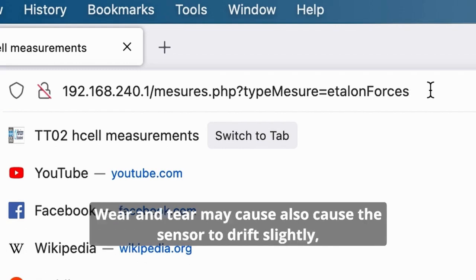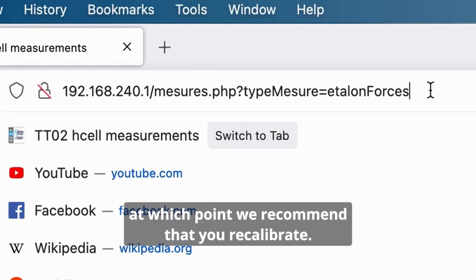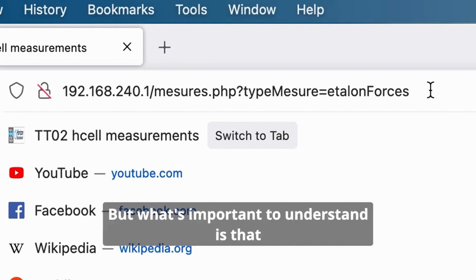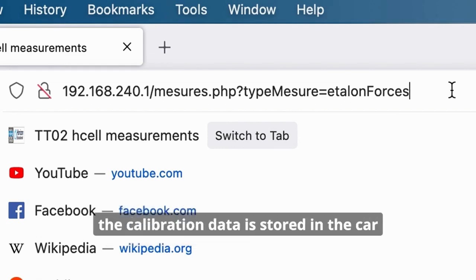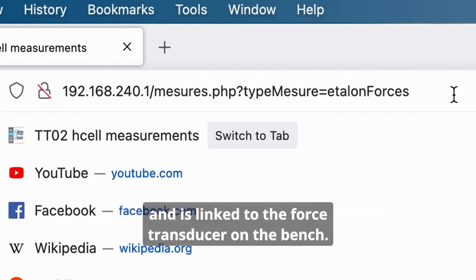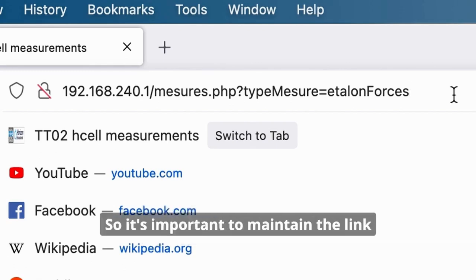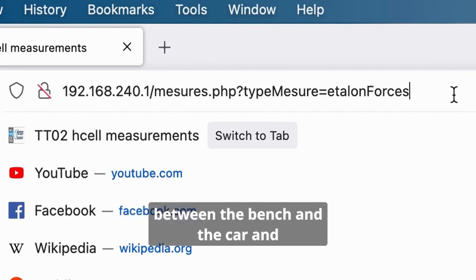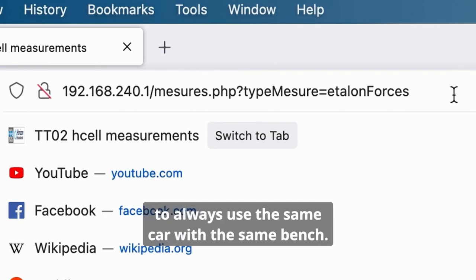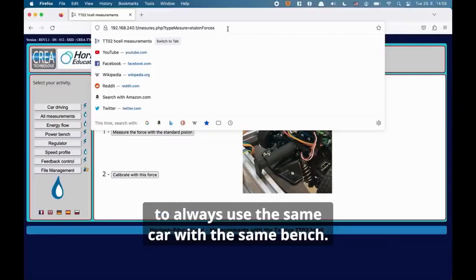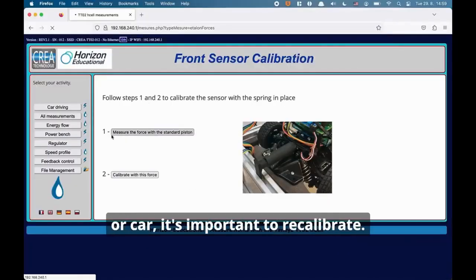The wear of the sensor can cause a very slight drift. At that point we recommend recalibrating. But what is important to understand is that the calibration data is saved in the car and is linked to the force sensor on the bench. So it is important to maintain the connection between the bench and the car, and if possible always use the same car with the same bench. If you need to change the bench or the car, then it is important to recalibrate.